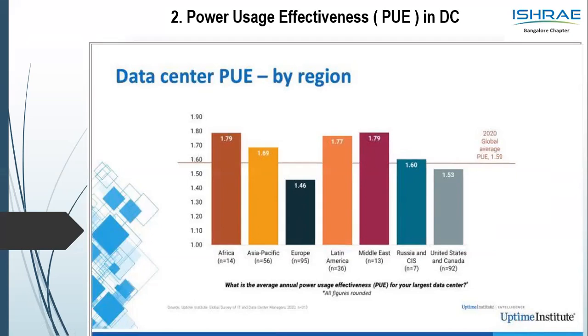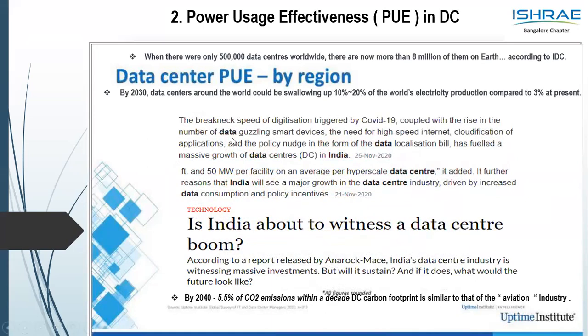So why are we talking about PUE? The very important factor is that, with the amount of social media and the amount of digitization, by 2030 the survey says data centers alone would consume 10 to 20% of the world's electricity. So PUE comes into the picture; we will have to keep a watch on the PUE. And by 2040 plus, the CO2 emission of data centers would be close to that of the aviation industry. Again, that's why PUEs are very important here. A couple of articles I picked up: with COVID and the pandemic, everything went online, digitization, and thereby the boom in data centers.